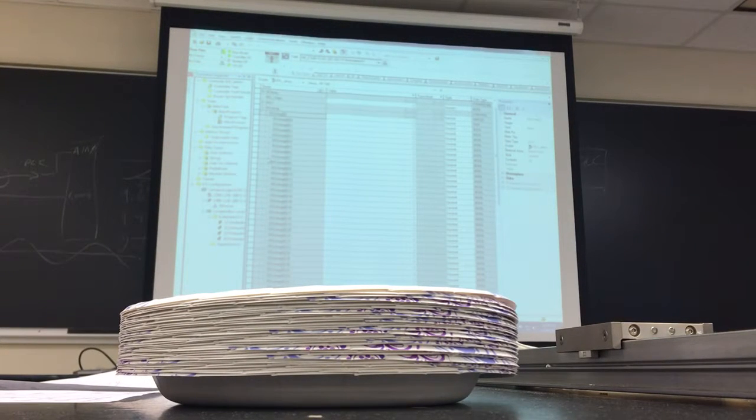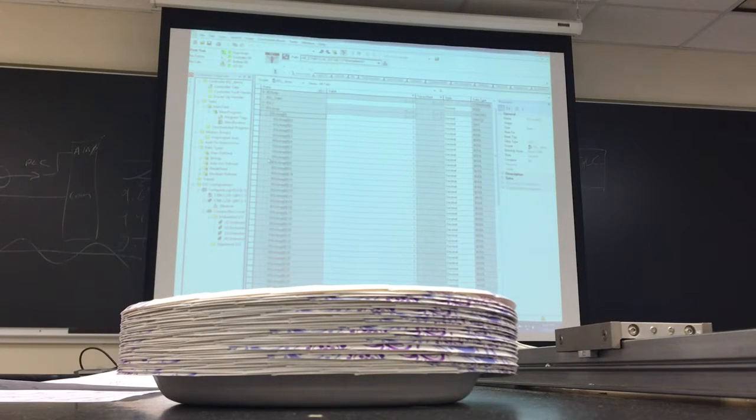So as it goes down here, when it gets to diverter 5, regardless of when I put this on, it's always diverting at the right time. If that pulse rate is too small, it's going to do weird things. If it's too big, it's not going to work some of the time. Right. And I can tell you, the pulse rate count is not between this photo eye and this photo eye, because that's 5,000 and change. Because I tested for that.